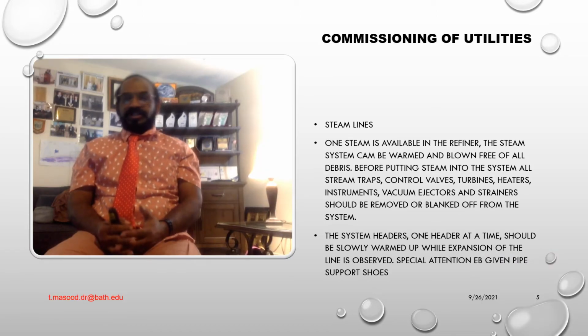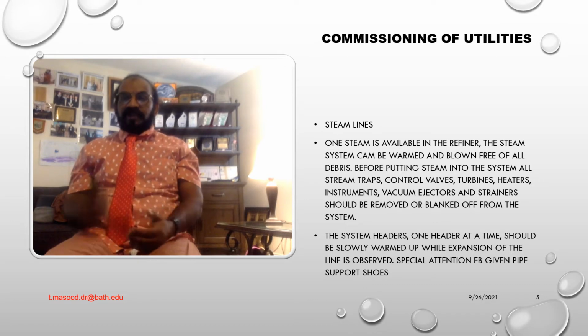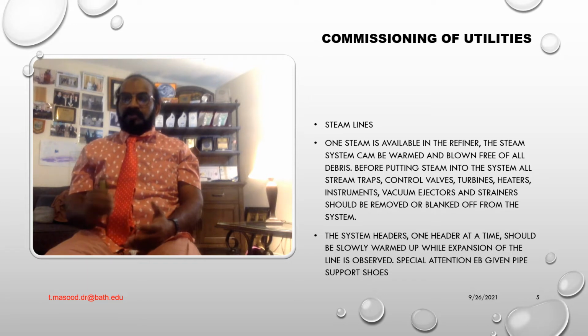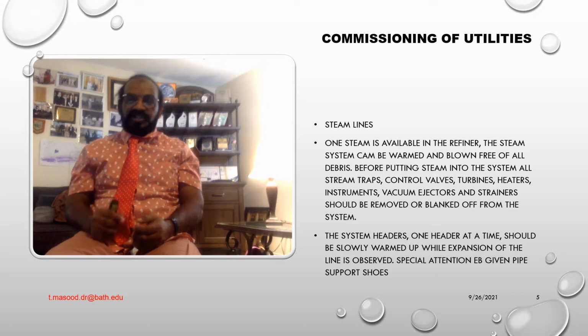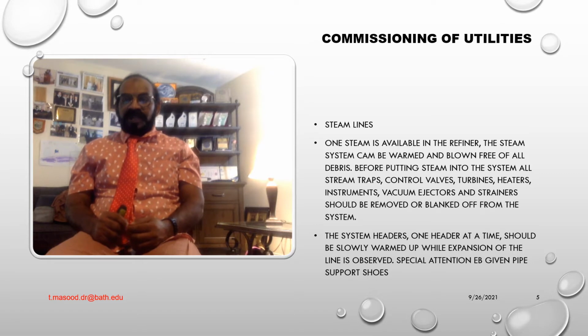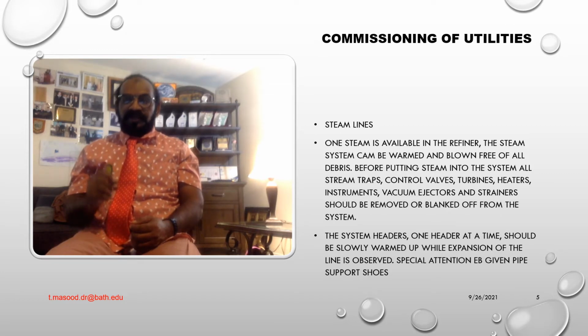Commissioning of utility steam lines. Once steam is available in the refinery, the steam system can be warmed up and blown free of all debris. Before putting steam into the system, all steam traps, control valves, turbines, heaters, instruments, vacuum ejectors and strainers should be removed or blanked off from the system. The steam header, one header at a time, should be slowly warmed up while the expansion of the line is observed. Special attention should be given to pipe supports. Note, condensate must be drained manually as it forms to prevent steam hammering.